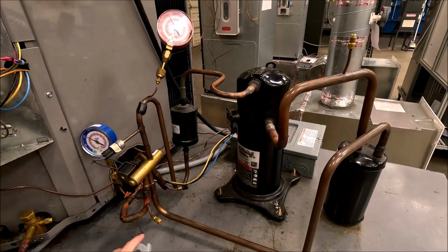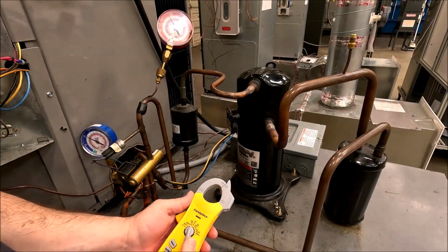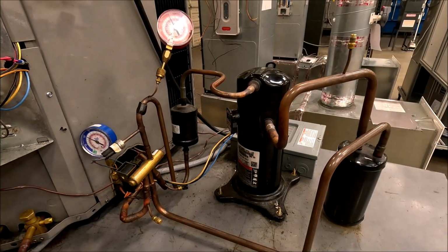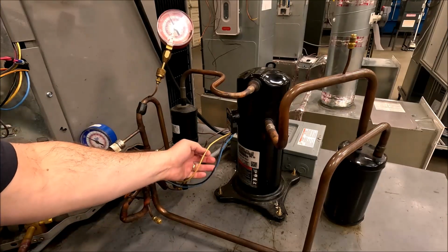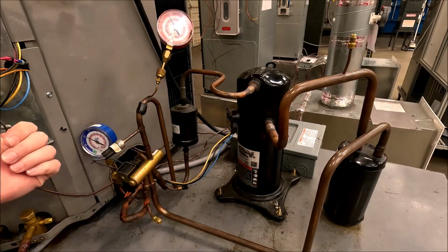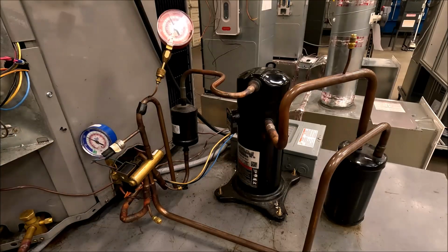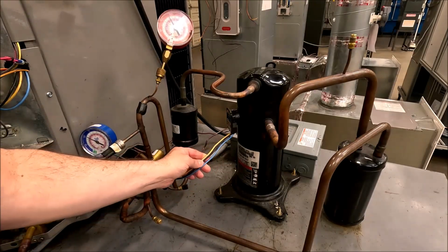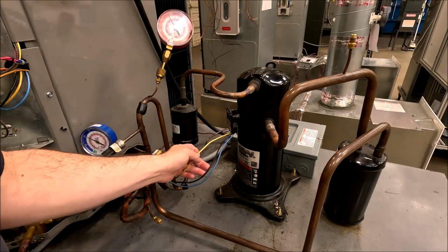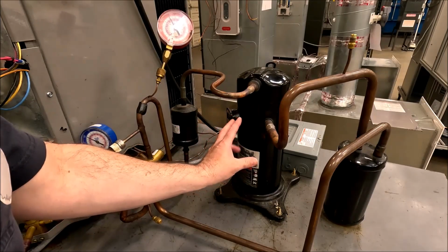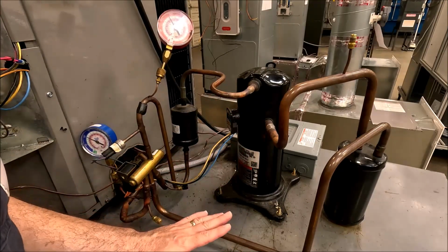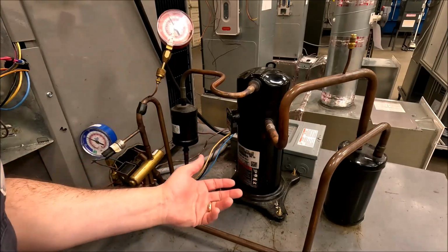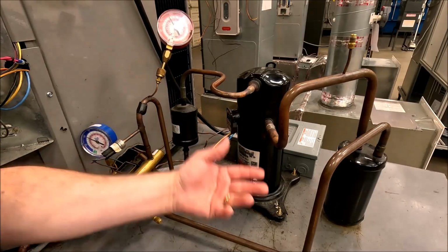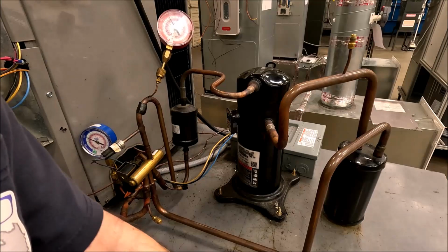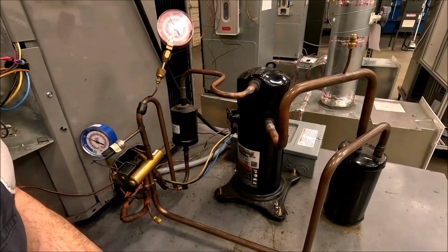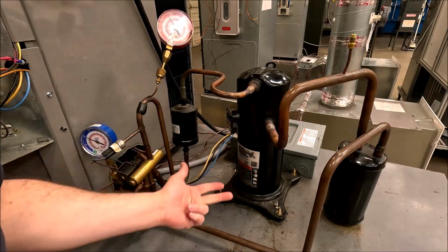All right, last one. Just so you get in my head a little bit here. So here I've got a PSC motor. I've got the capacitor over here in the unit to my left. And on this, you'll see 3 wires. Now this is a PSC motor. There's only 2 windings, not 3. You got to get into a 3-phase and some of your variable speed X13s before you get more than those 2 windings. But there are 3 terminals: common, start, and run.